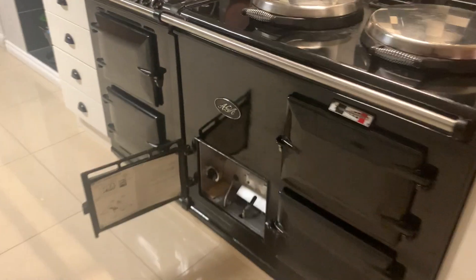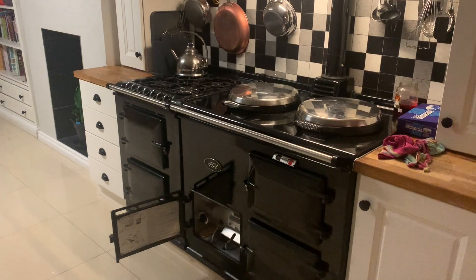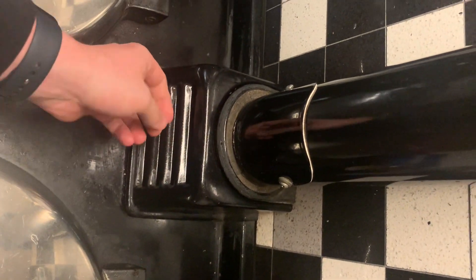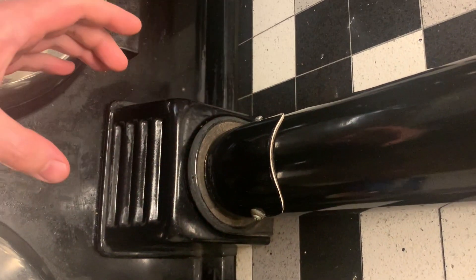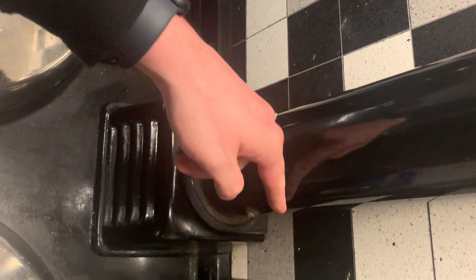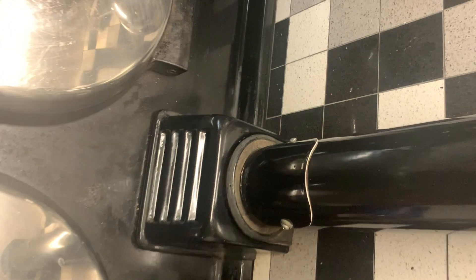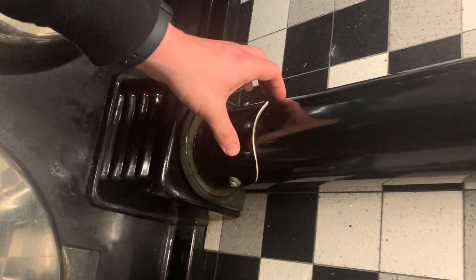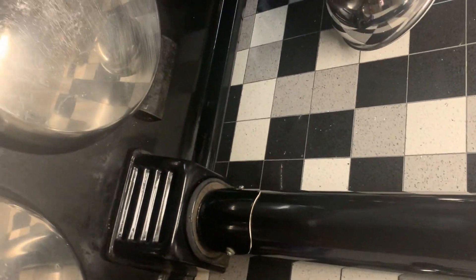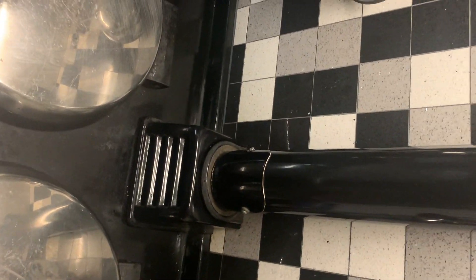Seriously hot. Just while I'm here — when it cooled, I literally pulled that out, took that screw off, took that screw off, took this plate out. There's a seal — it's actually a ceramic seal — and I bought one of those online. When I opened this up there was a huge amount of soot all the way up here, so I vacuumed that out.